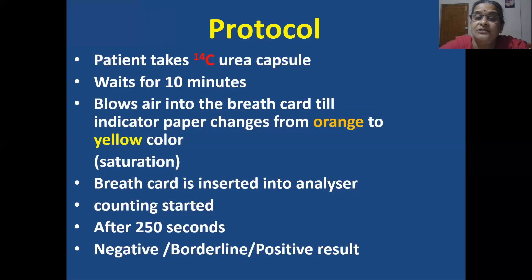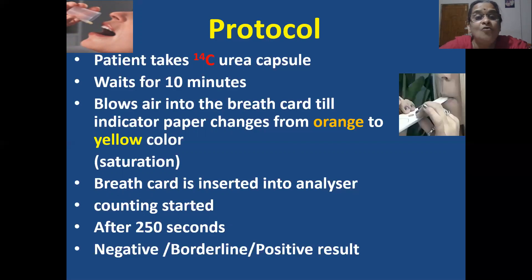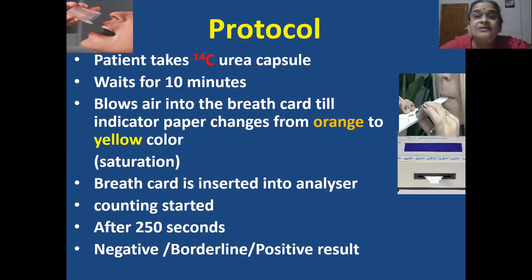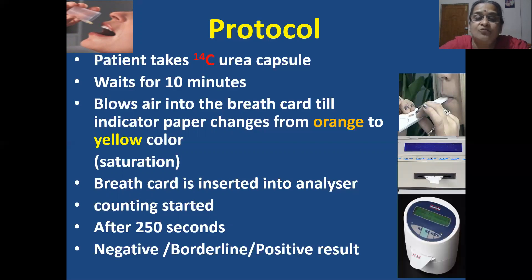The protocol: the patient takes a 14 carbon urea capsule, waits for 10 minutes, and blows air into the breath card until the indicator paper changes from orange to yellow to show saturation of the air — like a pH paper indicator. The breath card is then inserted into the analyzer and counting is started. After 250 seconds, a negative, borderline, or positive result can be detected.